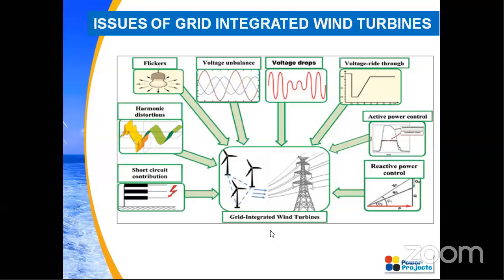Okay. So you can see the picture here, the grid integrated wind turbine. What are the issues they are facing? That is, what is the short circuit contribution? What will be the harmonic distortion? Flickers will be there, voltage unbalance will be there, voltage drops will be there. So voltage ride through compliance should be met, and active power control and reactive power control should be there. We are going to discuss all these issues in detail.